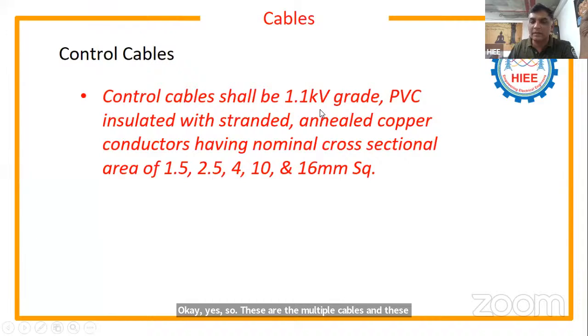Control cables shall be 1.1 kV grade PVC insulated with stranded annealed copper conductors. The nominal cross sectional areas will be 1 square mm, 1.5 square mm, 2.5, 4. Generally we use up to 4 square mm, 6 square mm for control cables. We generally don't go with 10 square mm and 16 square mm for control applications. Mostly 6 square mm is used for control cables.